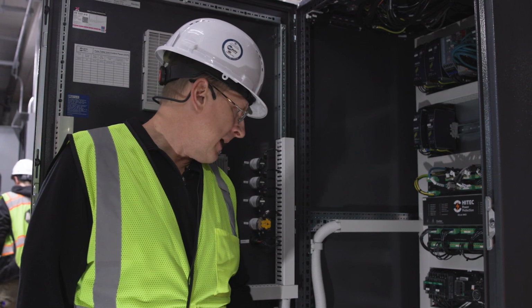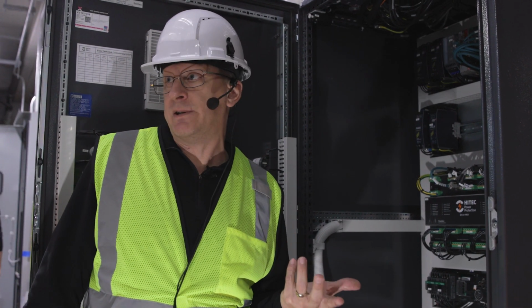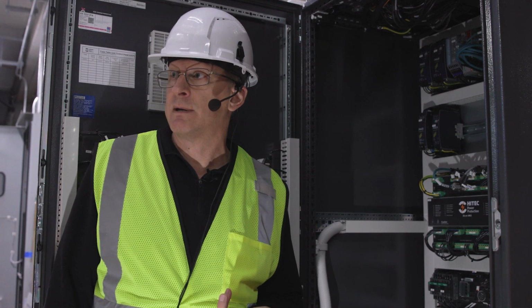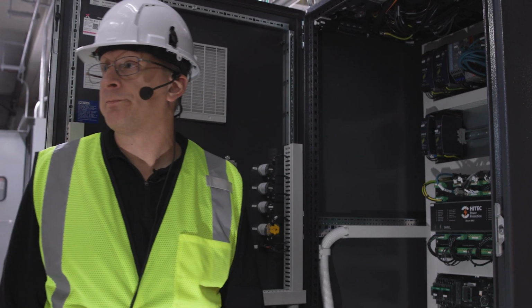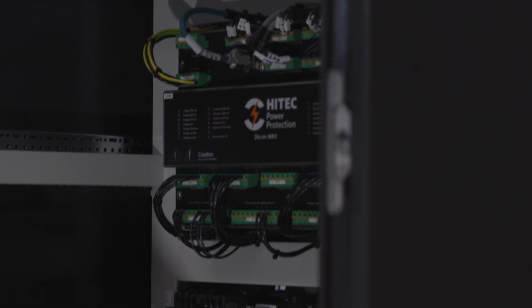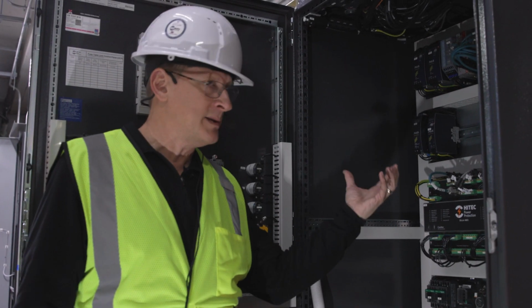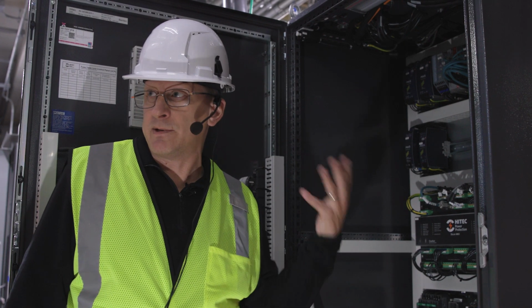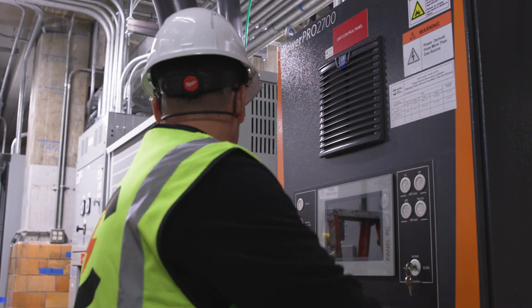So I would say it probably, if held to it, it'd last for about 20 or 30 minutes. Do we lose any programming if it goes dead? No, all the programming is permanent. All the settings and the programming are actually in the PLC. This is completely dark right now, so when we re-energize the mains and get power back to this unit, it'll come up. All the settings will be in it.